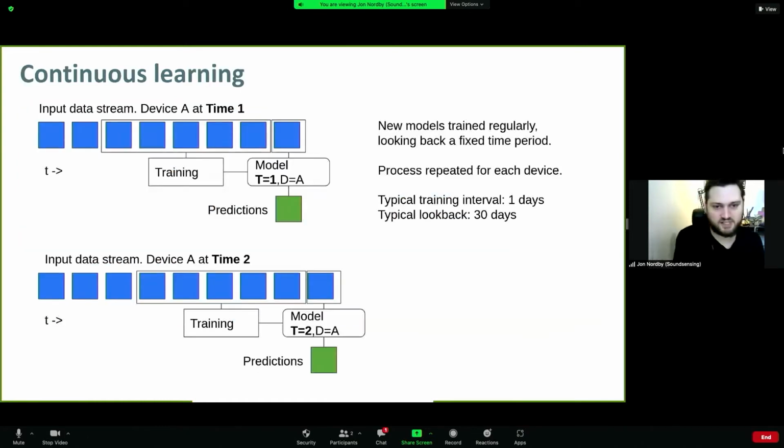Also important to understand in this anomaly detection world is that the models are not static, because the world is not static. So your office over a day has different operating patterns. For example, ventilation systems are typically off during the night because they don't need to run. It might have what's called demand controlled ventilation.